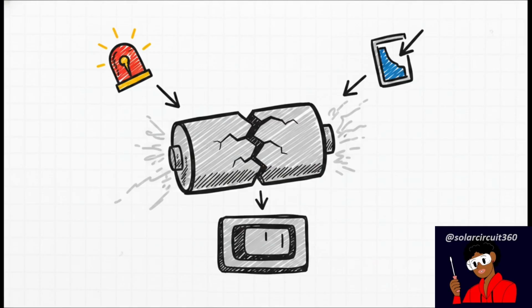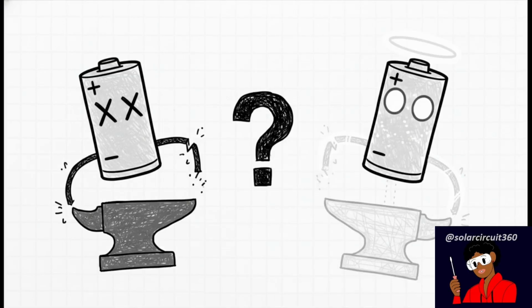A damaged cell is going to repeatedly drop significantly lower than the rest, no matter what its charge level is. It's going to trigger premature low voltage alarms. It'll eat into your total capacity, and eventually it'll cause your BMS to just shut the whole system down. Listen, balancing can fix an uneven state of charge, but it literally cannot repair a physically damaged cell that's suffering from capacity loss or major internal resistance issues.